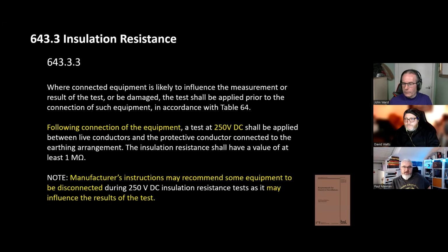However, where connected equipment is likely to influence the measurement or result of the test or be damaged, the test shall be applied prior to the connection of equipment in accordance with what we just saw, table 64. Following connection of the equipment, very important wording there, that's new. Following connection. So that infers, don't just lash everything in and connect it up and then test it. So they're trying to pull people back. It then says a test at 250 volt DC shall be applied, but you still have 1 meg, which goes against table 64, because table 64 says 0.5 at 250.